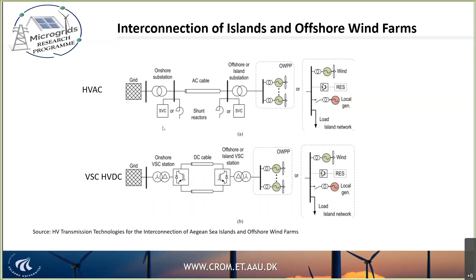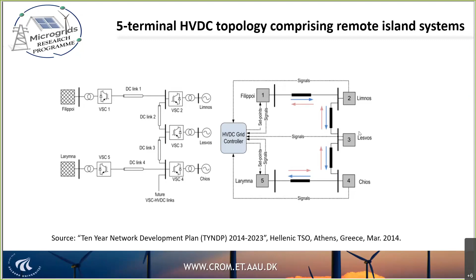We have a similar thing if we think about DC, however we may not have this kind of compensation of reactive power or harmonics. And this is how they finally solved it: it's a 5-terminal HVDC topology. I think it's very attractive because here you can see a couple of grid connections through HVDC, and then here you have 3 generators also coming with this DC link, and finally here you have the HVDC grid controller. As you can imagine, inside these boxes what we have is droop controllers, very similar to what we have in DC microgrids.